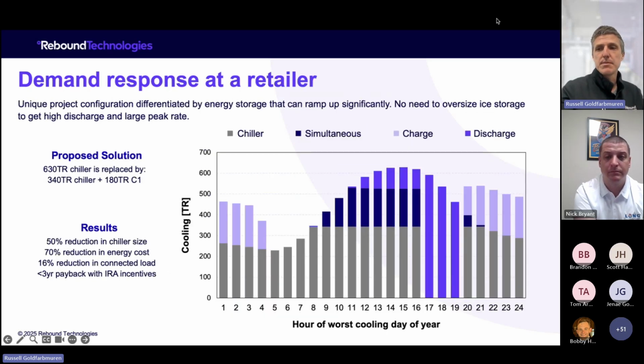So to go through some examples really quick, this is a retail example where the volatility here is created by demand response. And so what we're able to do is, during this 3-hour window in the afternoon, deliver 600 tons of cooling where a traditional ice storage system would not be able to ramp up to that amount of cooling without being really oversized.